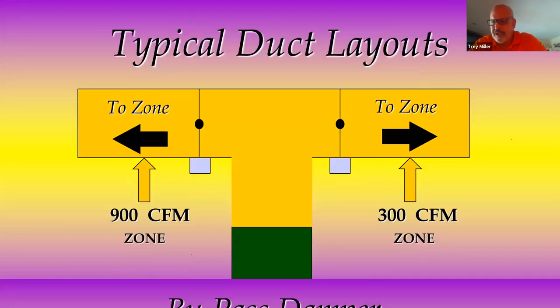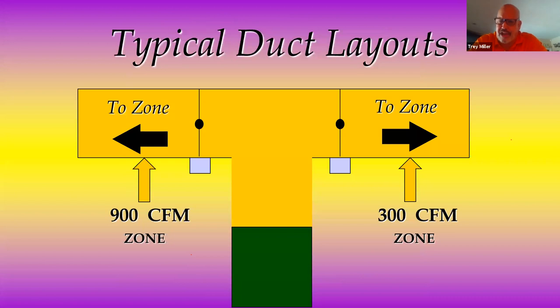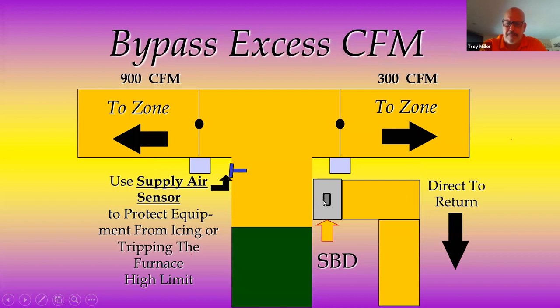First of all, let's just look at zoning in general and bypass in general. We've got a 900 CFM living area. We've got a 300 CFM sleeping area. Every night you go to bed, why in the world am I going to heat and cool the entire home? So I'll shut this damper and I'll blow 1200 CFM through ductwork sized for 300. Of course, that's wrong. You cannot. We have to release the excess pressure. This is where we will use the bypass damper, a smart bypass damper, and bypass the air right back into the return.